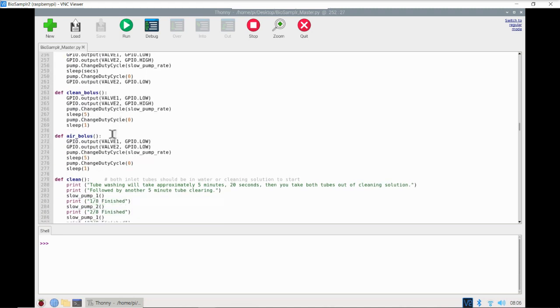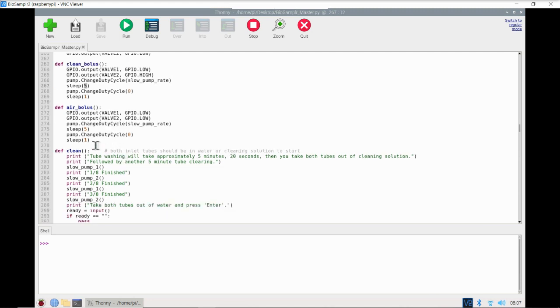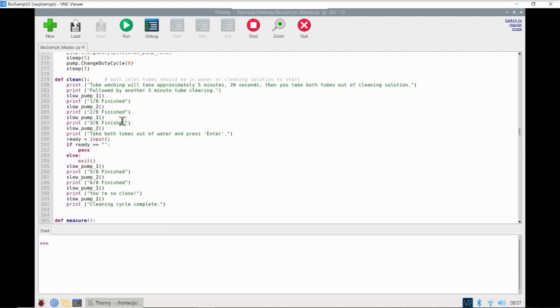Clean bolus and air bolus: clean bolus moves a bolus of cleaning solution through the sample tubing for five seconds — that is where you define the size of that bolus. If you want to increase the bolus size, you increase that value. Same with air bolus — you're moving a bolus of air through the tubing. The clean function is a cleaning cycle used after a sample process run to clean your sample tubing.